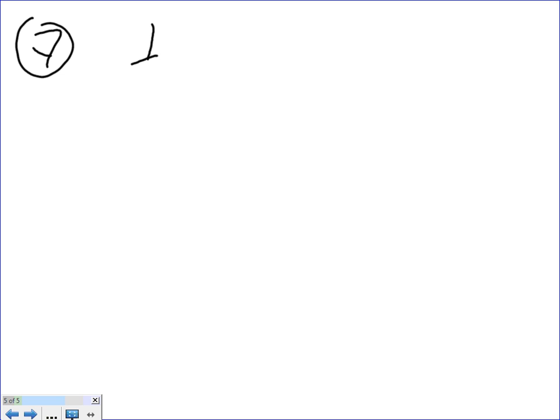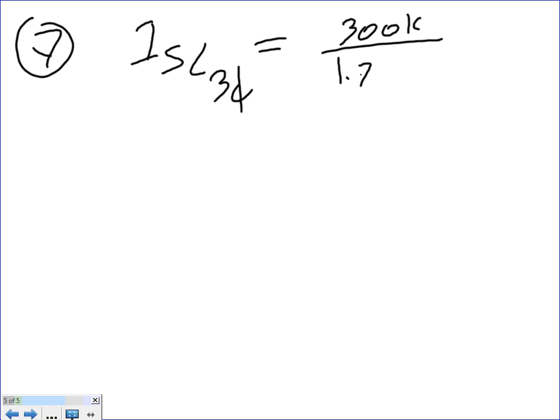I secondary line, now there's a 3-phase component. I secondary line for the 3-phase equals 300K divided by 1.73 times the voltage on the secondary—240. If you do the math on this one, it's going to be 723 amps, the secondary line current coming from the 3-phase.